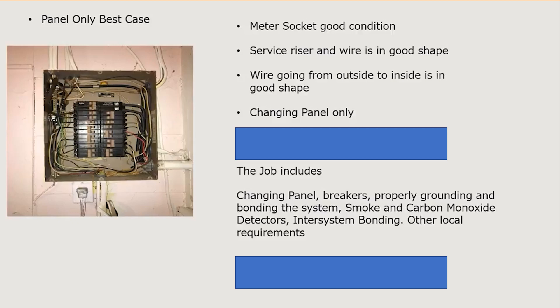The panel-only job includes the panel change, breakers, properly grounding and bonding the system, smoke and carbon monoxide detectors, inter-system bonding, and other local code requirements. The estimated cost is $1,800 to $3,000 labor plus parts and permit. Estimated material is between $800 and $2,000, depending on the inflationary market and permit costs. None of these scenarios include arc fault and ground fault breakers — if those are needed, add $1,500 to $2,000 depending on how many arc fault breakers are required.